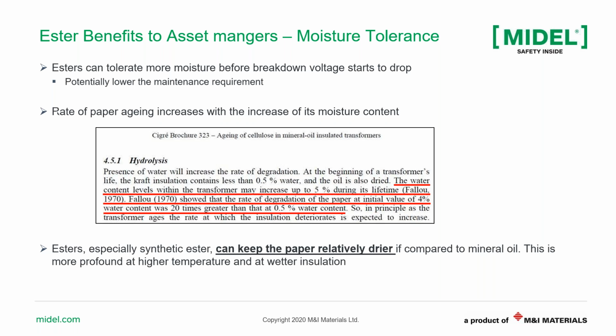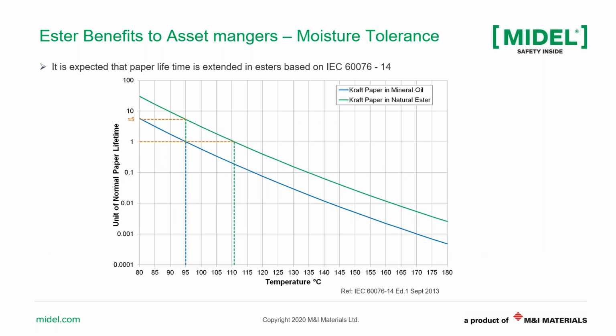And so asset managers can benefit from extending the life of the assets when, say, retrofilling a wet transformer. The ester can dry that transformer a little bit more, I mean the solid insulation, and aid in extending its lifetime. I was wishing for more time to show more detail on this, so I thought one representative curve to show the impact of esters on extending the lifetime of the transformer is this curve.